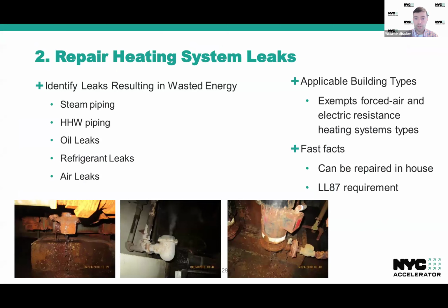Measure number 2 is to repair heating system leaks. The idea here being that if you have a steam leak, a heating hot water leak, a domestic hot water leak, any types of leaks, something's probably broken, you're using more energy than you need to, and fixing and addressing those issues is going to be beneficial. So this is going to apply to many types of building systems, whether you're using steam, whether you're using hot water. It's not going to apply to forced air buildings that distribute conditioned air through ductwork, and it's also not going to apply to buildings that are heated through electric resistance. Oftentimes, this work can be completed in-house if you have building staff who are capable of doing some light plumbing work or something like that, and it does also overlap with Local Law 87 requirements.